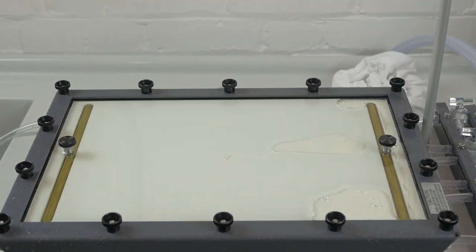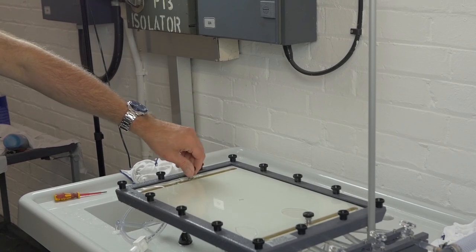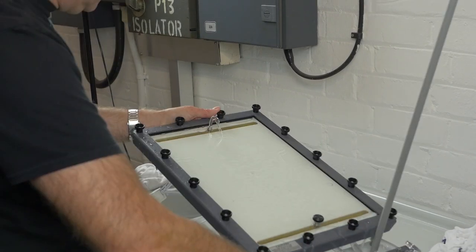Connect your water supply to allow flow through the apparatus. Remove the downstream purge screw and block the drain outlet, forcing the trapped air and some of the water out through the purge screw.